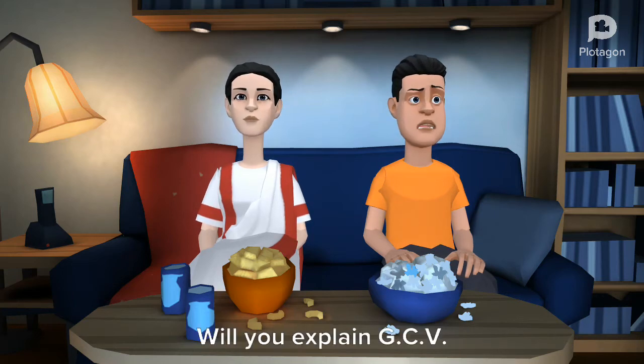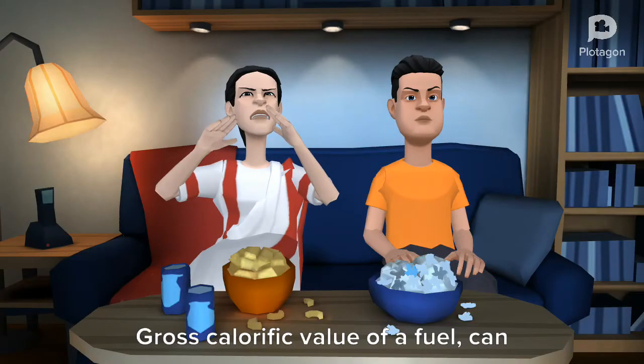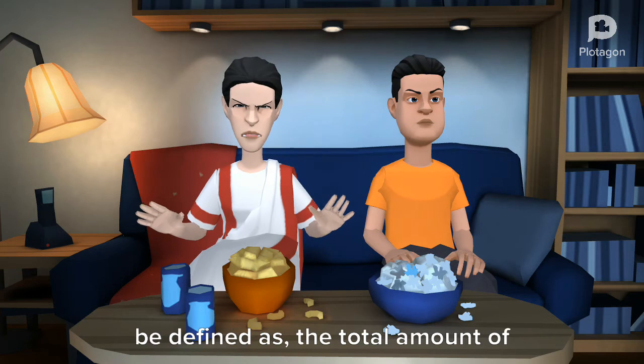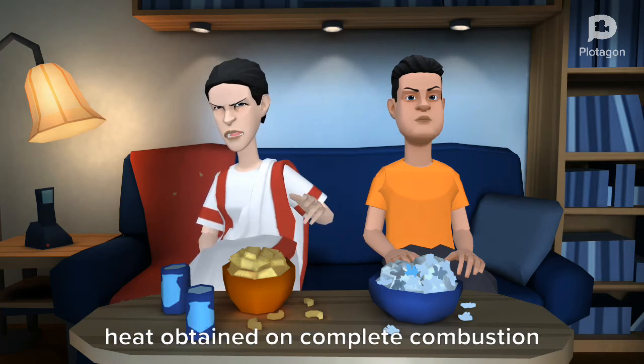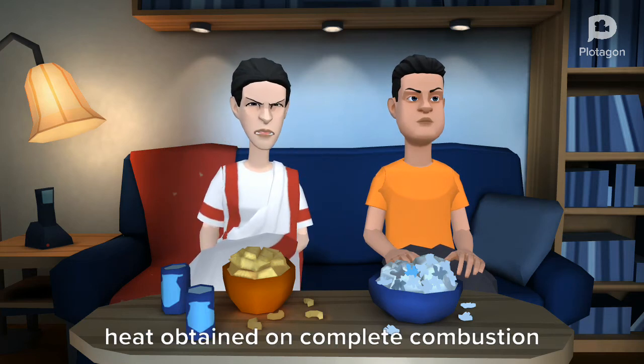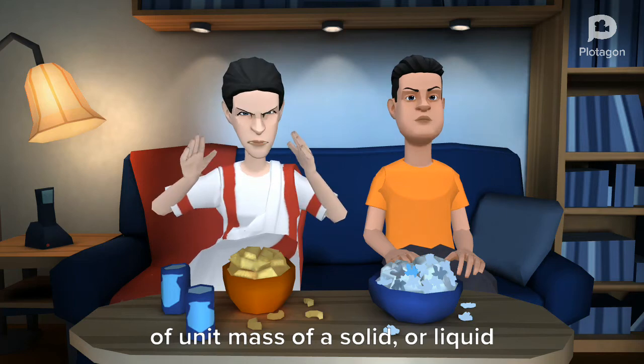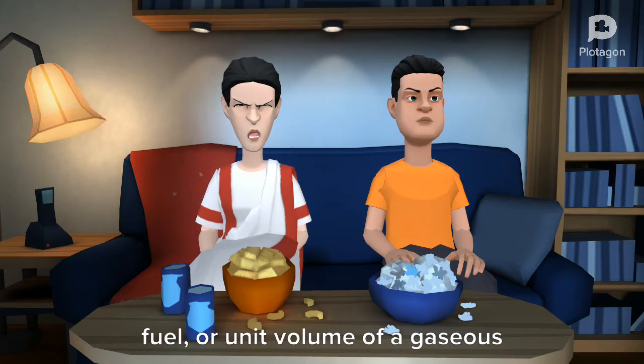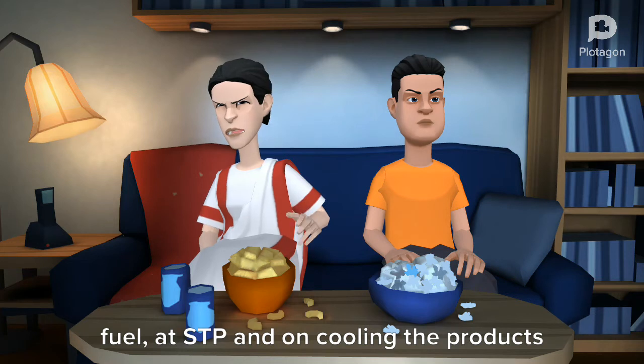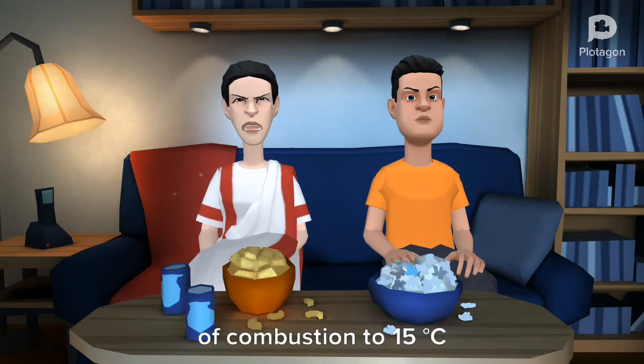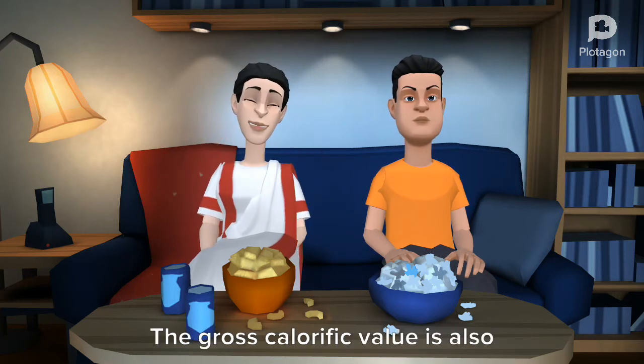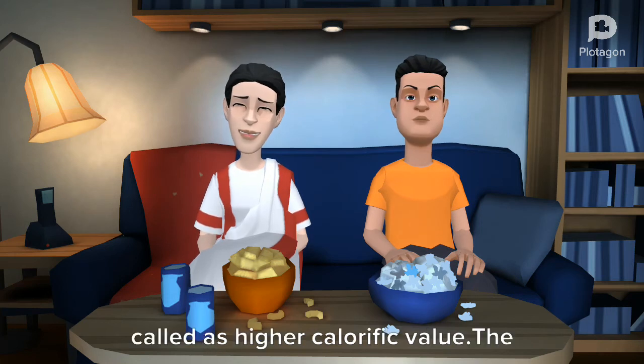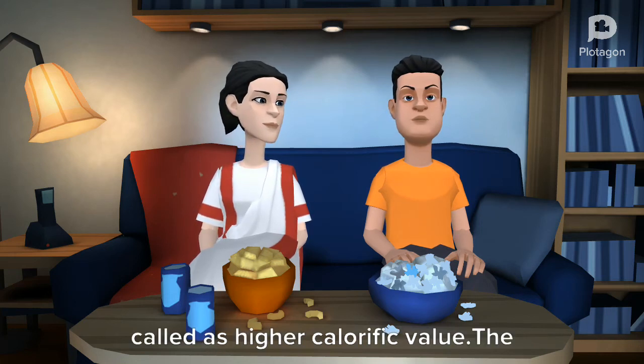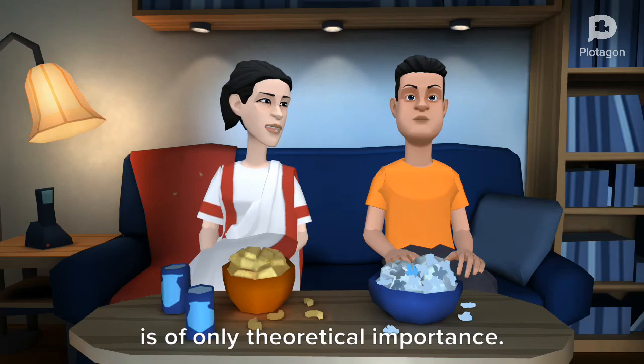Will you explain GCV and NCV? Gross calorific value of a fuel can be defined as the total amount of heat obtained on complete combustion of unit mass of a solid or liquid fuel, or unit volume of a gaseous fuel, at STP and on cooling the products of combustion to 15 degrees Celsius. The gross calorific value is also called higher calorific value. The GCV is of only theoretical importance.